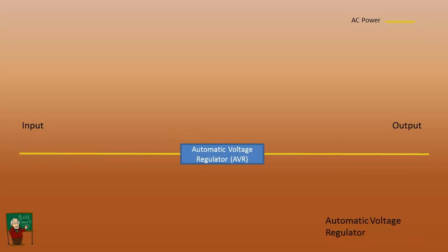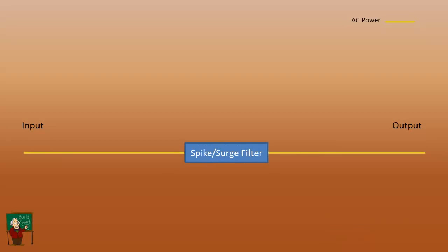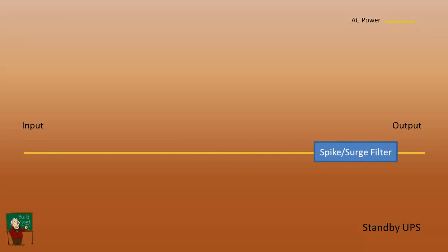Next thing we'll look at is an automatic voltage regulator. This comes in a variety of forms. It's been around for quite a while. Essentially, we power this up, and when we have a larger incoming voltage, the output stays essentially the same. And also, if we go with a lower input voltage, again, we'll step it up so that we have essentially the same output voltage. Now we'll take that surge filter, move it to the end, and take a look at a standby UPS.